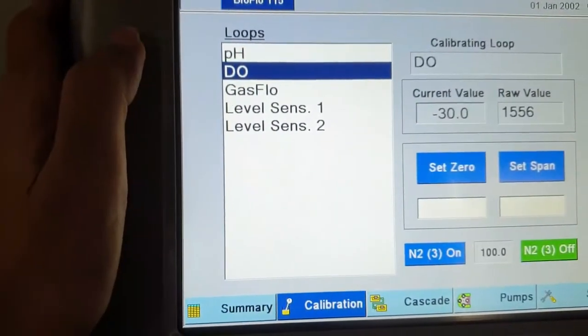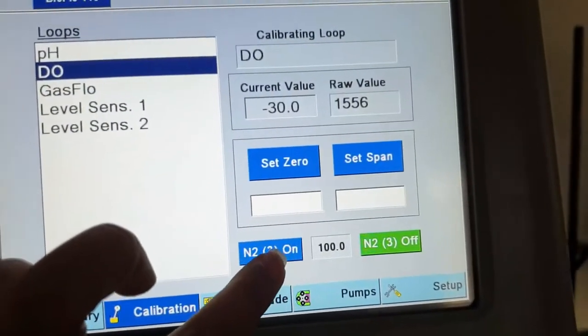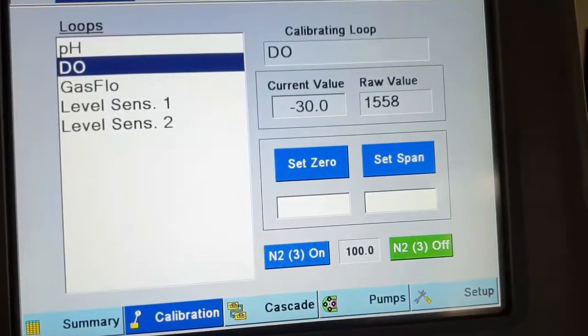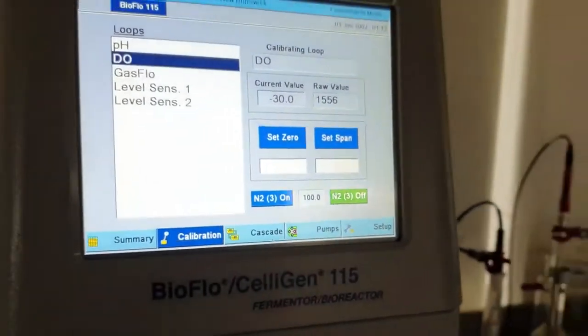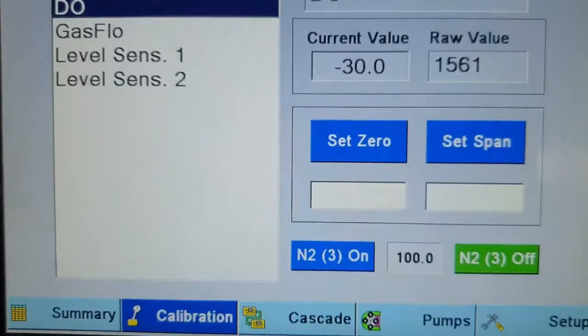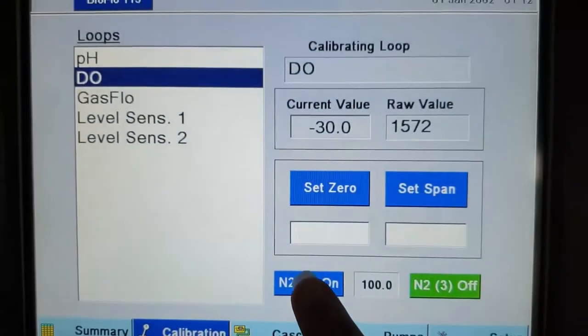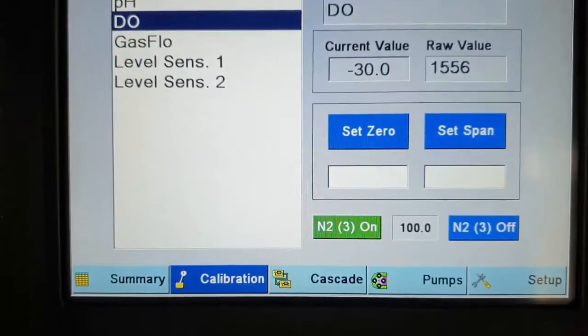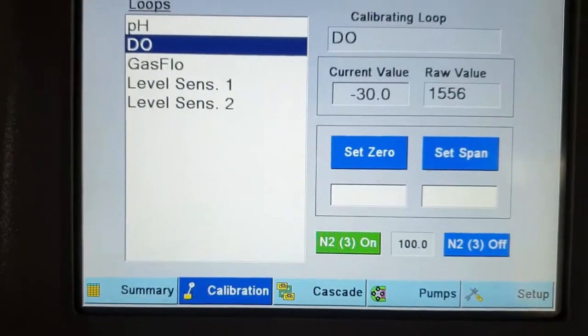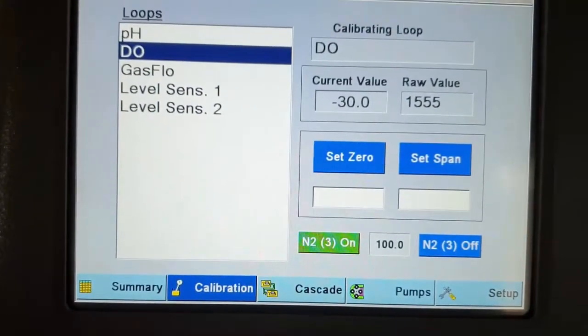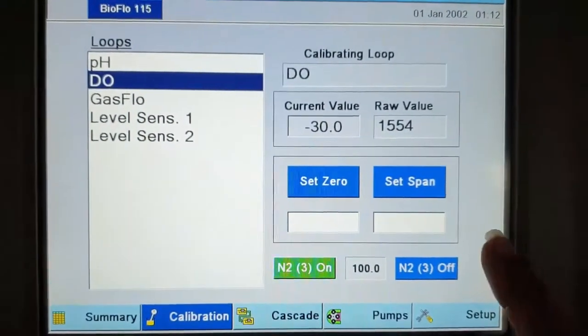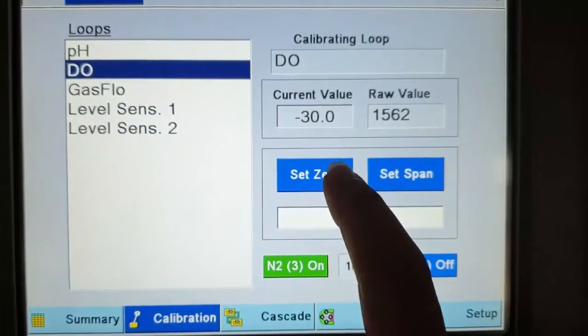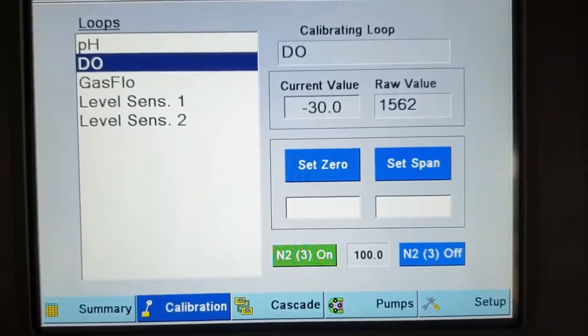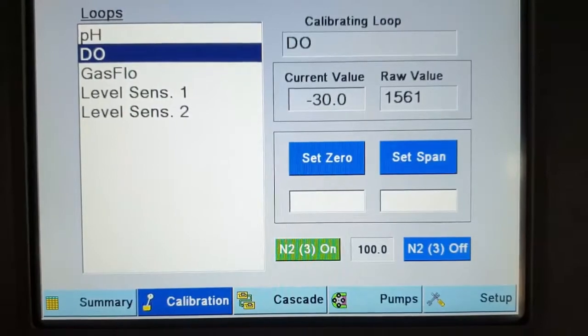For calibration, I need to go to the dissolved oxygen, turn on the nitrogen, but before that I need to open the valve of the nitrogen. Okay, I need to turn on the nitrogen. This should be continued for 8 minutes. So after 8 minutes I will turn off the nitrogen and set 0. This will be the 0 point of the probe.